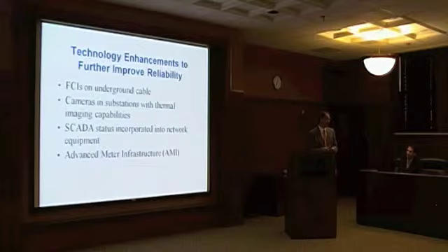Another effort underway, working with our security team, is putting some cameras in some of our in-feed substations where we receive power from TVA. The cameras we've chosen to use there not only have that security aspect, they also have thermal imaging capabilities. We can scan our equipment and look for hot spots, which in the electric industry is a signal that you've got something going on you need to address. So when these cameras are up and running, we will have that forewarning before we have any equipment failure.